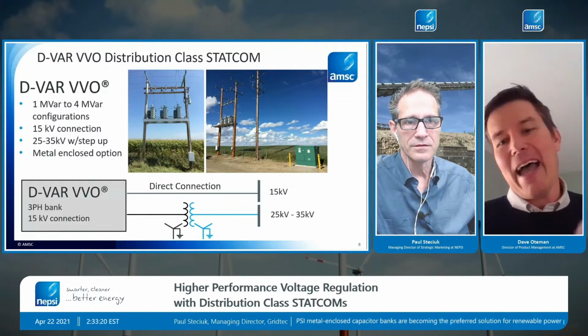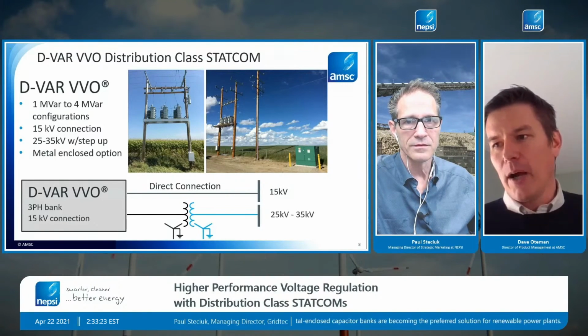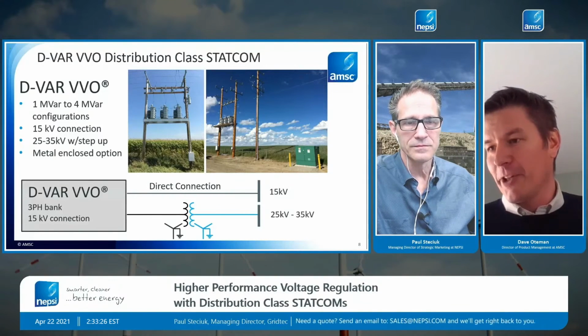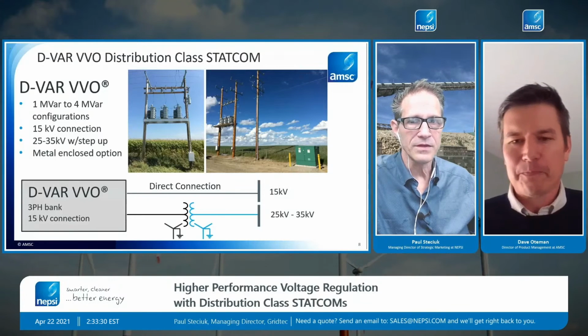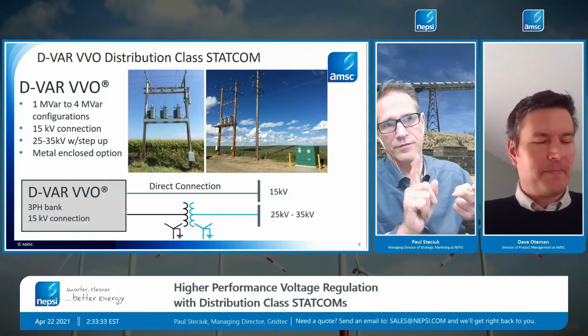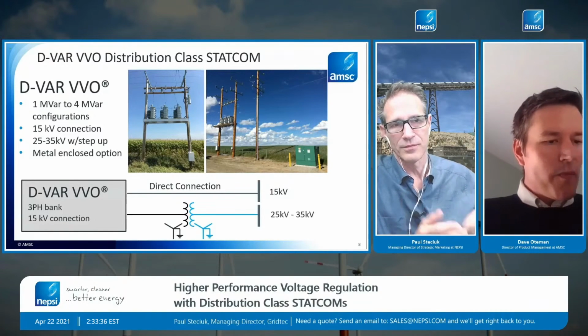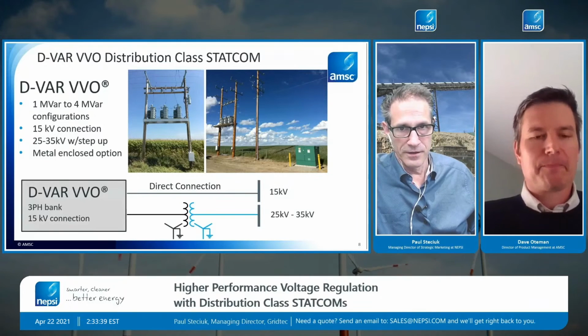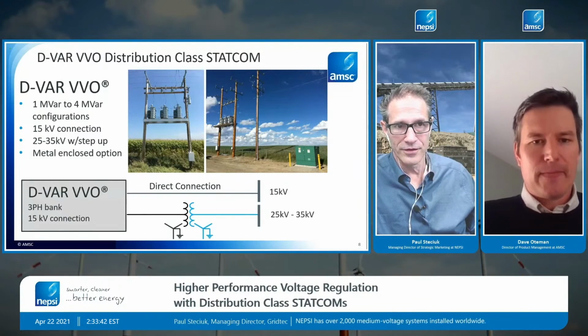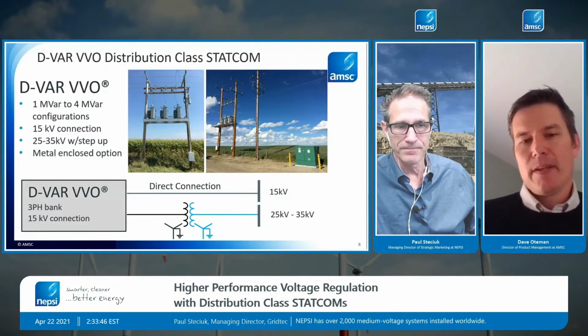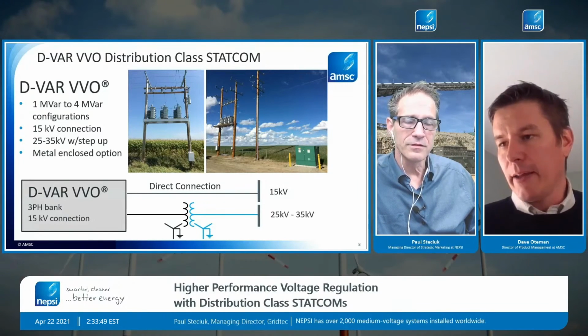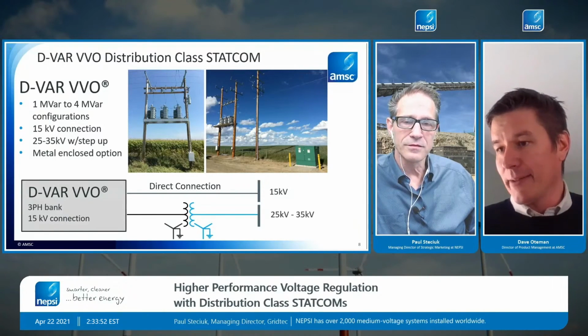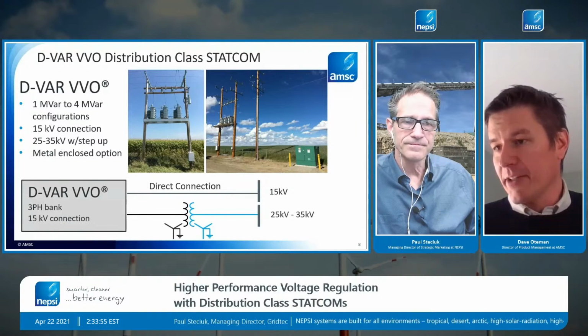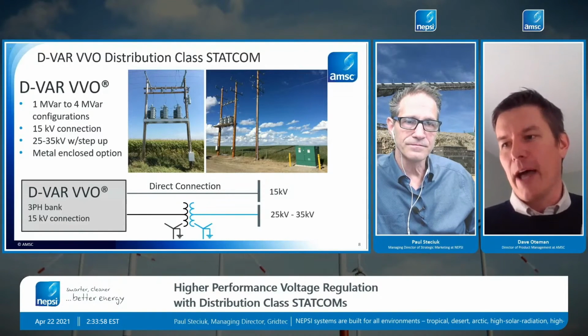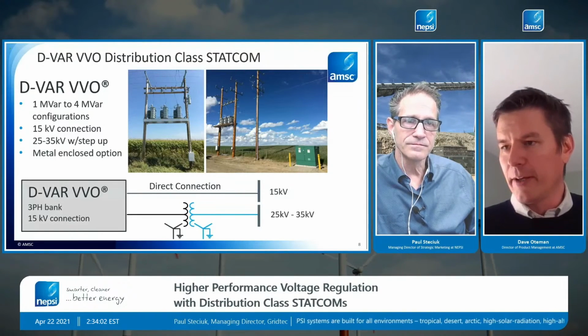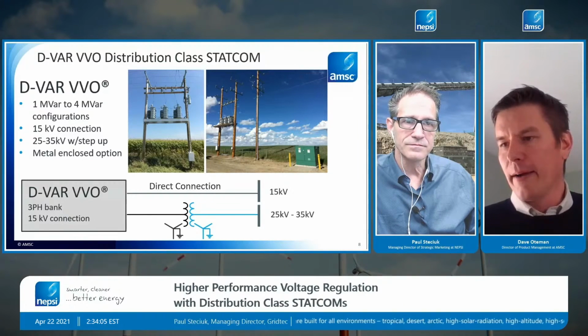As 25 kV distribution grows, we'd like to replicate the 15 kV version at 25 kV, but that's down the road a bit. So it's 12.47, 13.2, 13.8 kV type distribution systems, primarily 4-wire multi-grounded neutral. The VVO can also be floating Y. The installations shown in this picture are grounded Y, but we also have floating Y installations especially for 3-wire systems, common in Europe, the UK, and Australia. So either floating or grounded Y are supported.